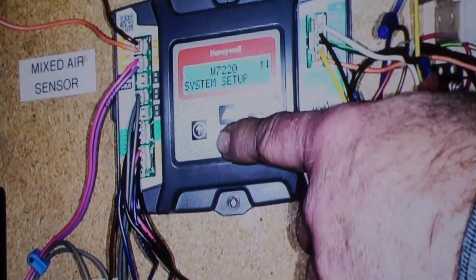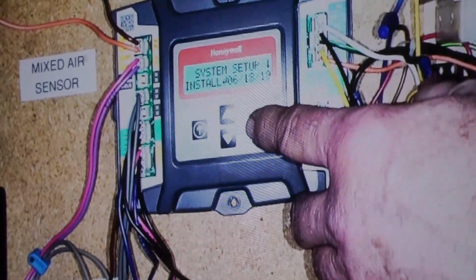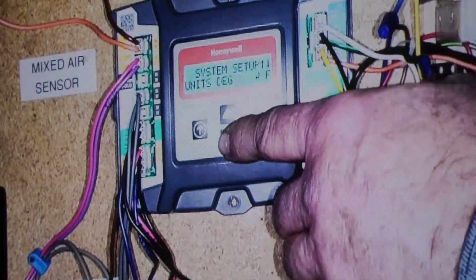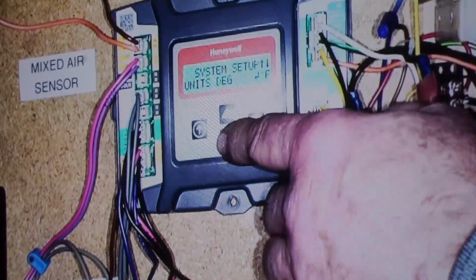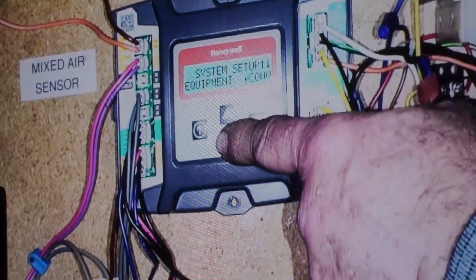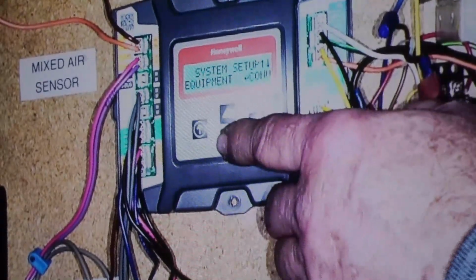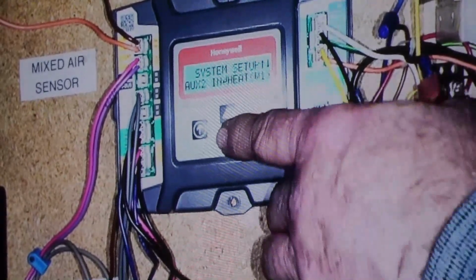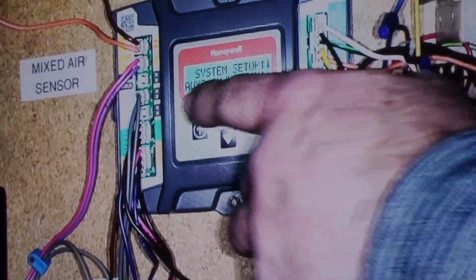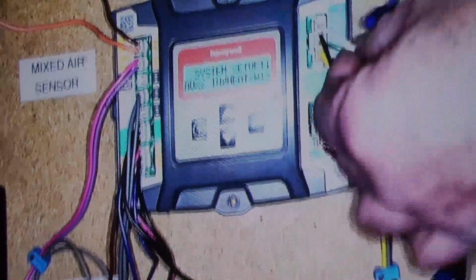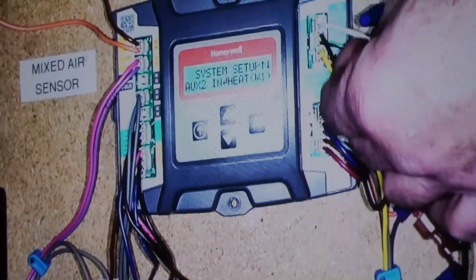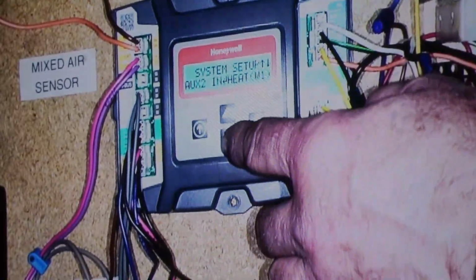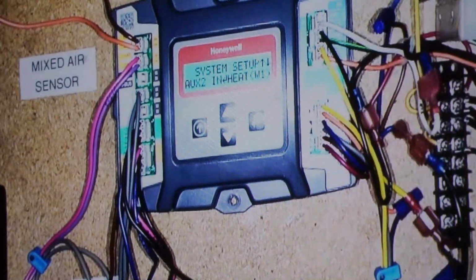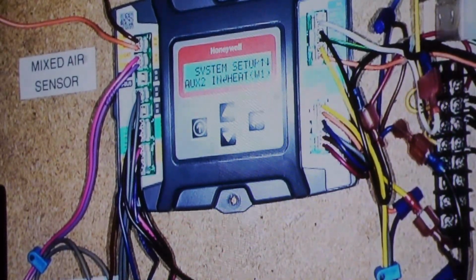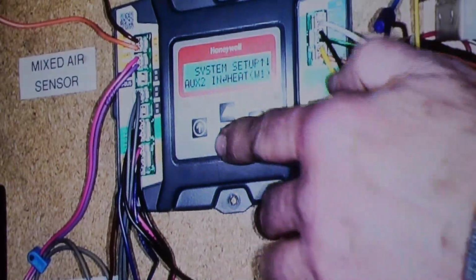The next one is system setup. My install date, my units of measure. We're not Canadians, so we're going Fahrenheit. Nothing against Canadians. Conventional heat cool. Auxiliary 2 is our W call, or our W. This is just so it knows it's in the heating mode. And on a staged air volume, we're always at high speed in a heating call. So that's all that's for.